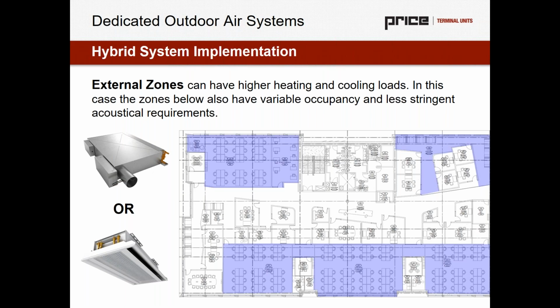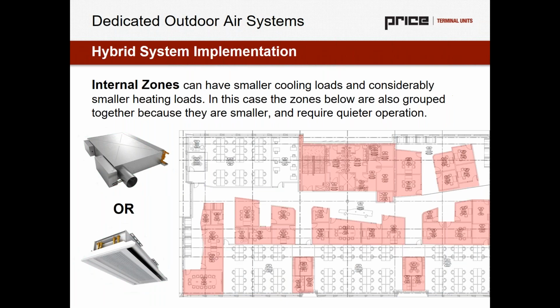So it's an interesting question. The reality is, I would say both are a great option. I would tend to lean more towards utilizing fan-powered units on these exterior zones, but I think that both can work. Now let's consider internal zones. So internal zones can have smaller cooling loads, considerably smaller heating loads. In this case, the zones below are also grouped together. They're smaller and they tend to be quieter because they're offices, or meeting rooms or phone rooms, things of that nature. In this case, would we consider putting FP for fan powered or CB for chilled beam?